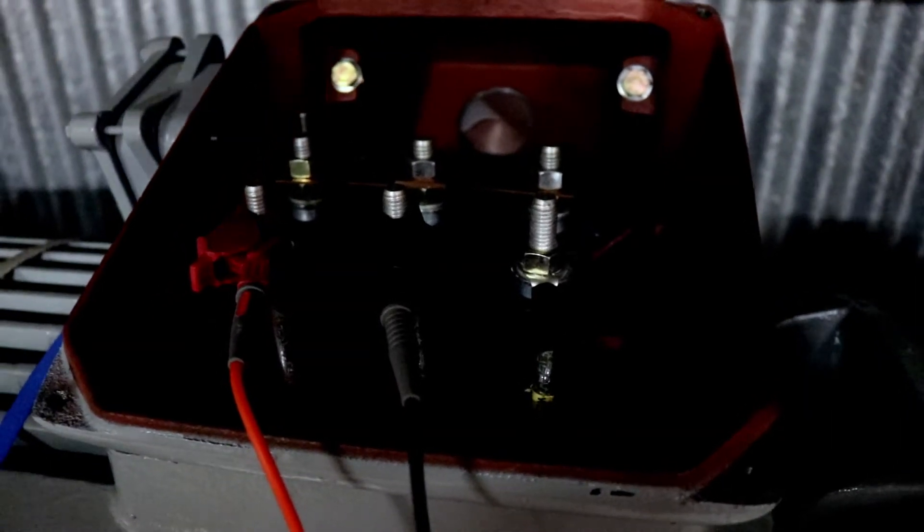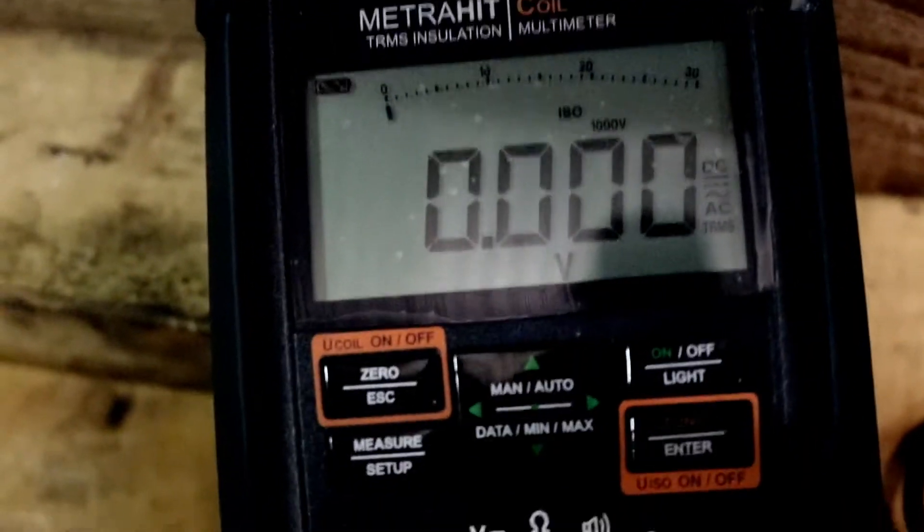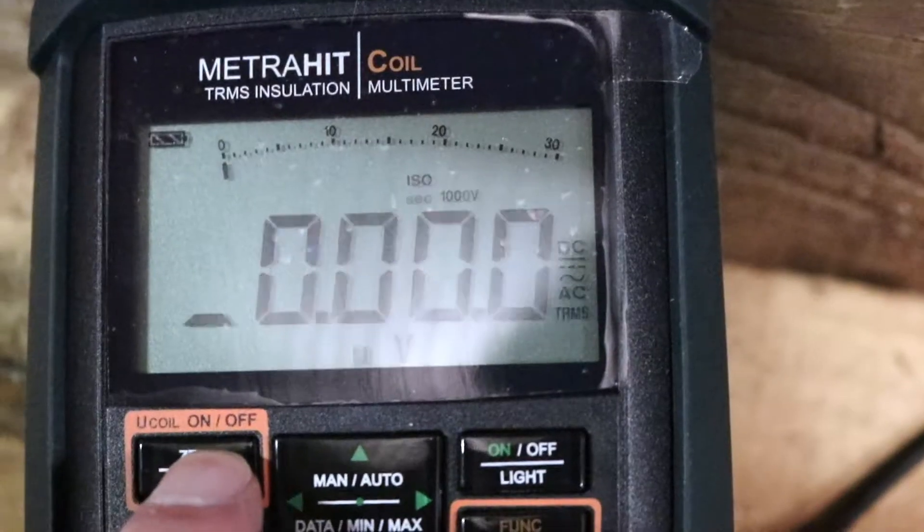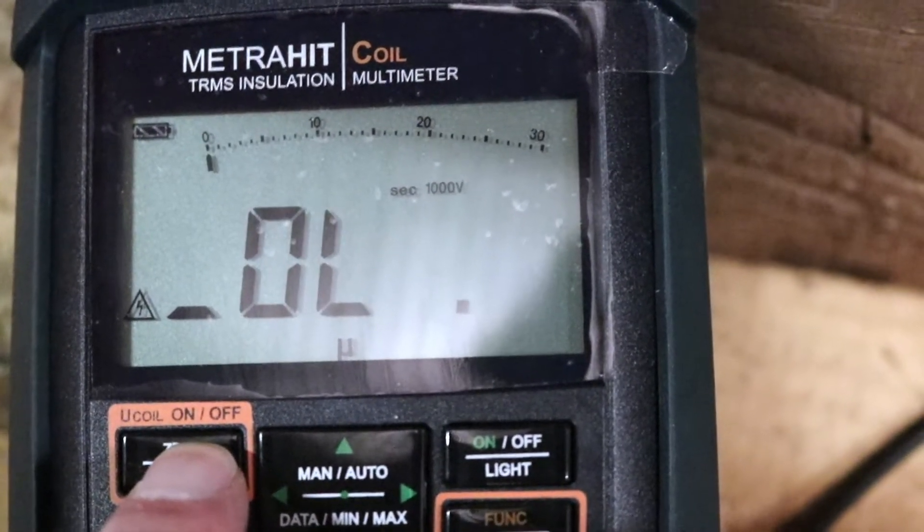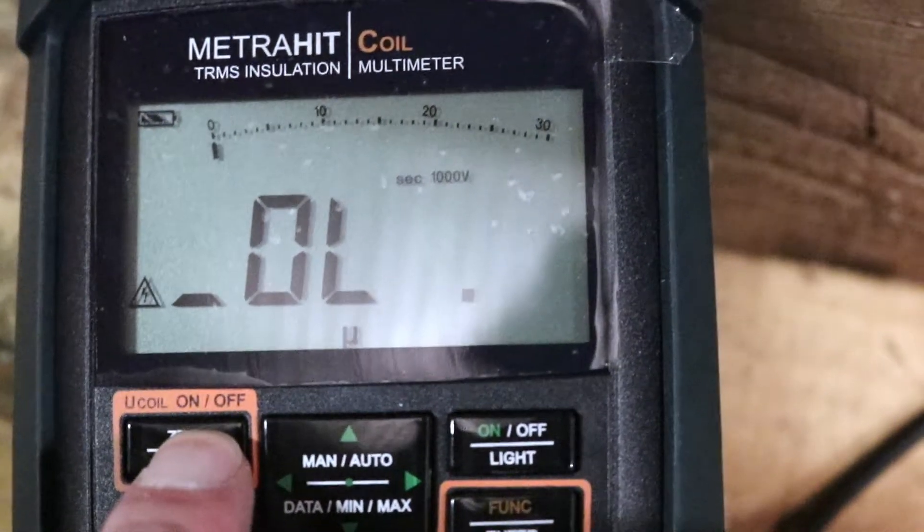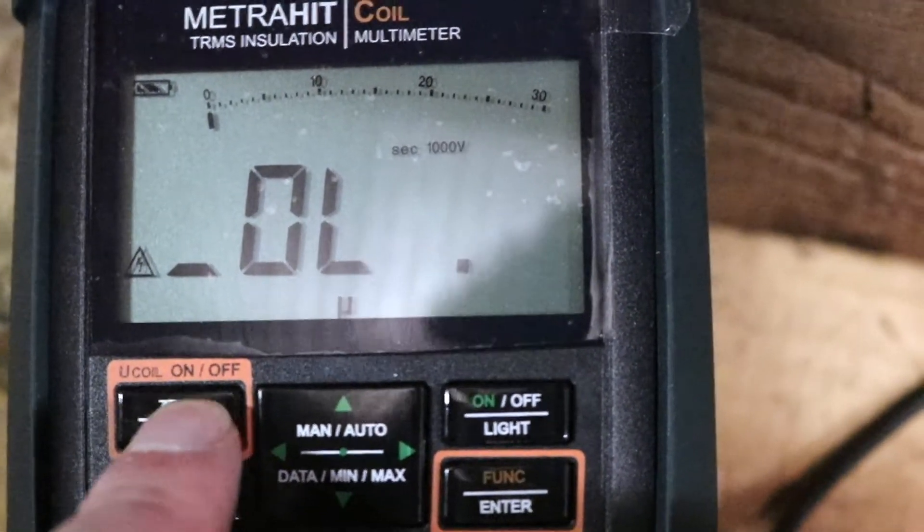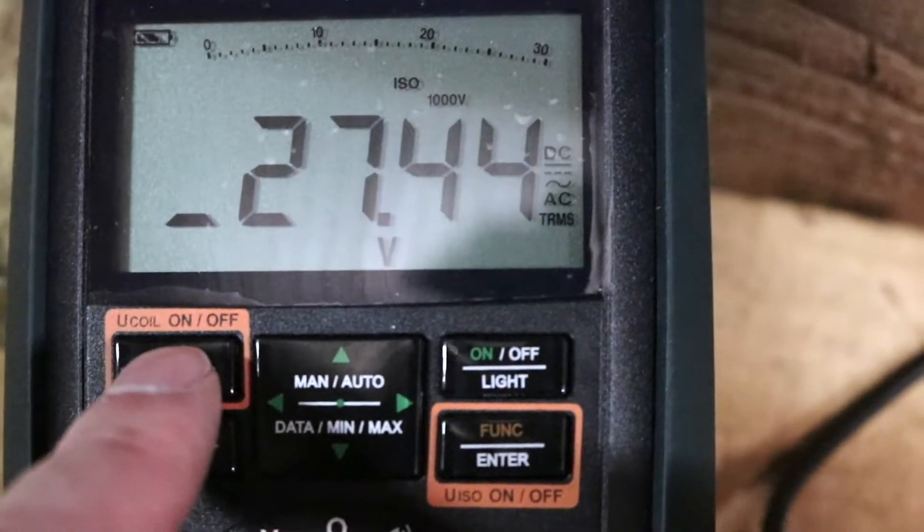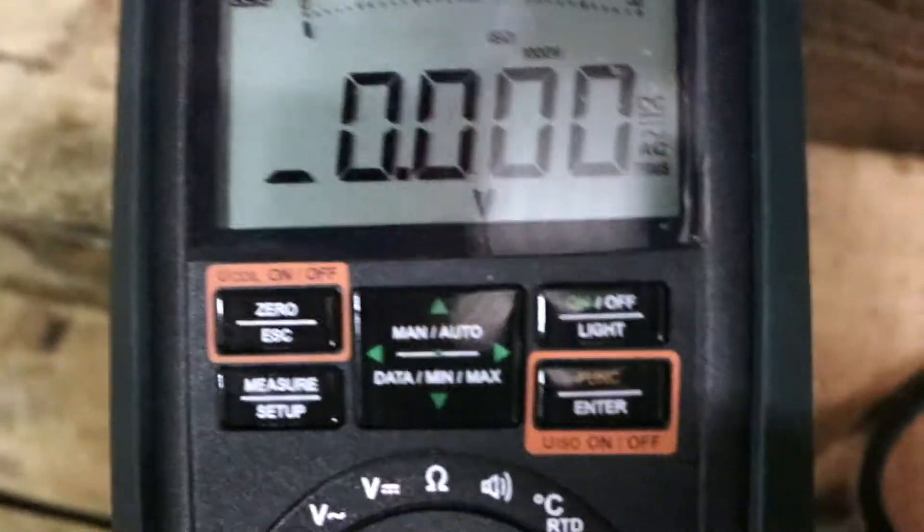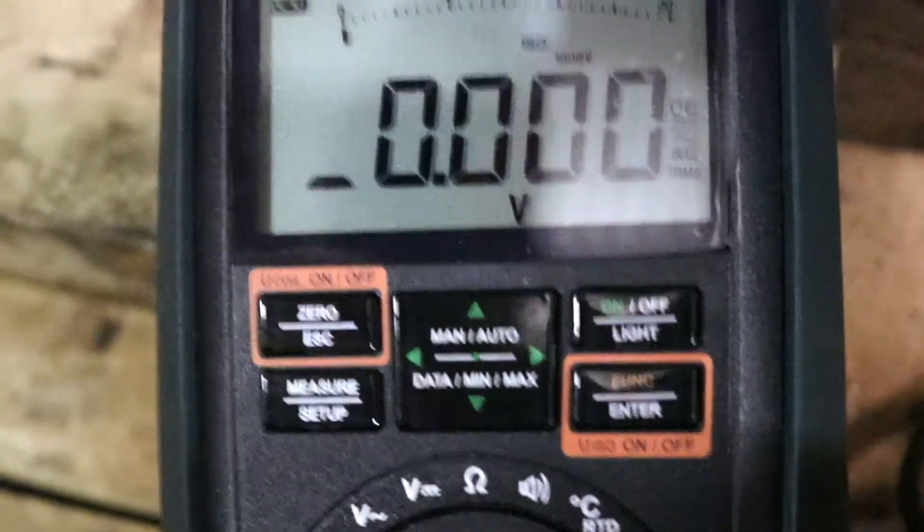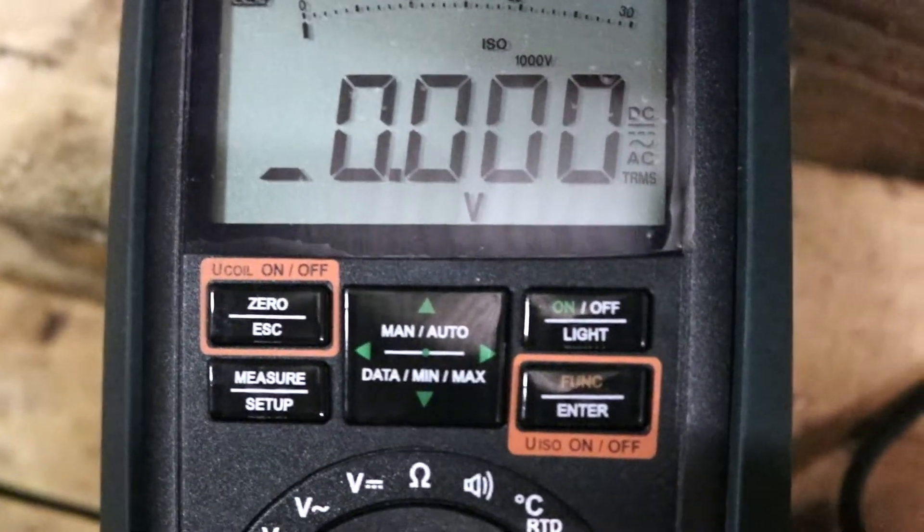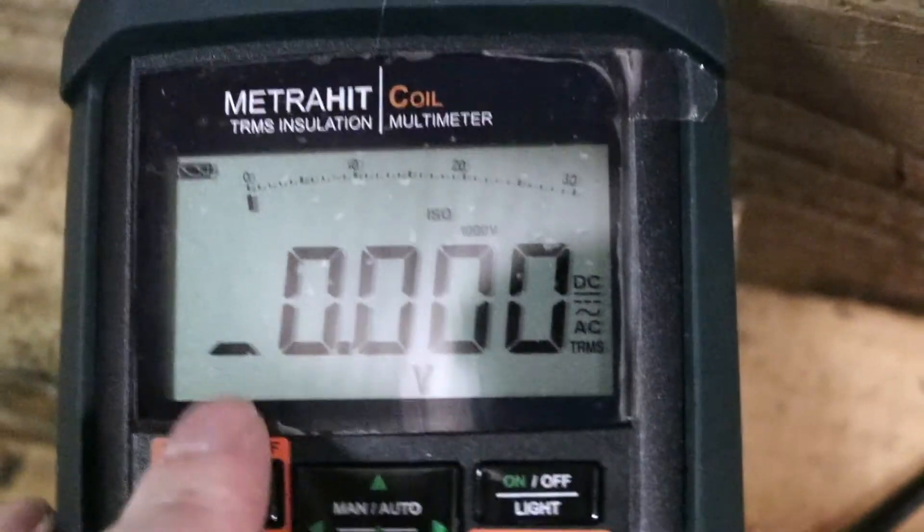Motor is now wired up in star. First two connections on the UV. And we'll go for the coil test again. It doesn't seem to work. The motor is wired in star.